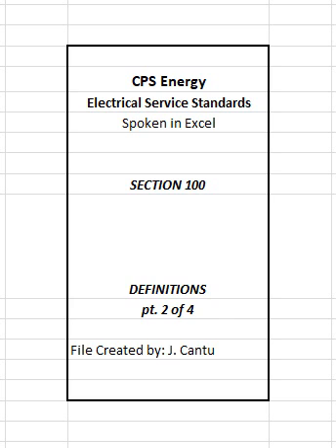Instrument transformer. A transformer that reproduces in its secondary circuit in a definite and known proportion, the voltage or current of its primary circuit with the phase relation substantially preserved. Current transformer, CT. A CT is an instrument transformer used for measurement purposes and is designed to have its primary, highest current, winding connected in series with a circuit, the current of which is to be measured.